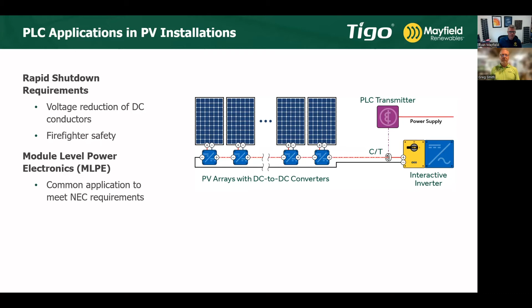So when we're using module level power electronics and we add these PLC transmitters, what we're doing is inducing that signal onto the conductors so that we can control the rapid shutdown devices, or control the circuits. Ultimately, that's what code is saying - we have to control the circuits, and this gives us a way of controlling the circuits to meet the rapid shutdown requirements.